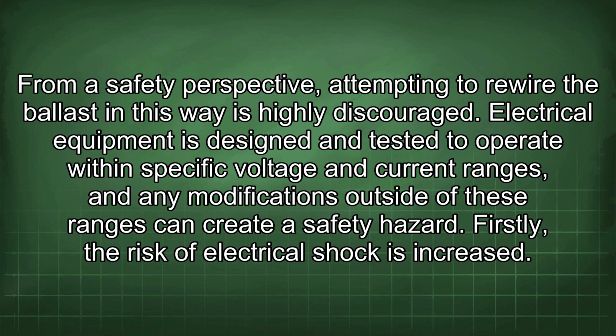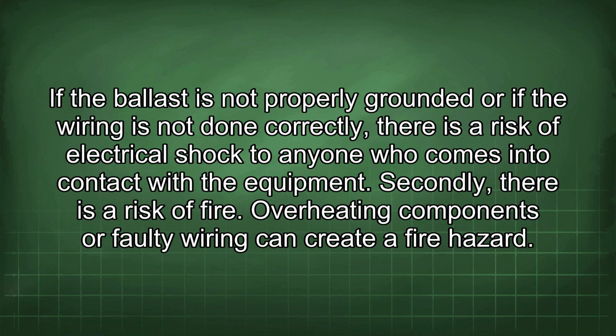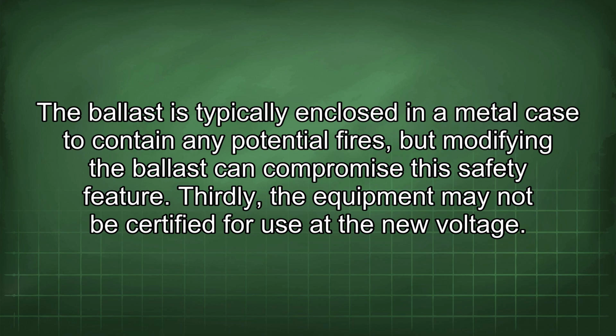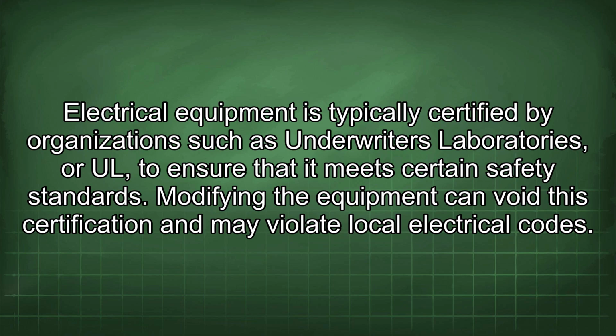Electrical equipment is designed and tested to operate within specific voltage and current ranges, and any modifications outside of these ranges can create a safety hazard. Firstly, the risk of electrical shock is increased. If the ballast is not properly grounded or if the wiring is not done correctly, there is a risk of electrical shock to anyone who comes into contact with the equipment. Secondly, there is a risk of fire. Overheating components or faulty wiring can create a fire hazard. The ballast is typically enclosed in a metal case to contain any potential fires, but modifying the ballast can compromise this safety feature. Thirdly, the equipment may not be certified for use at the new voltage. Electrical equipment is typically certified by organizations such as Underwriters Laboratories, or UL, to ensure that it meets certain safety standards. Modifying the equipment can void this certification and may violate local electrical codes.